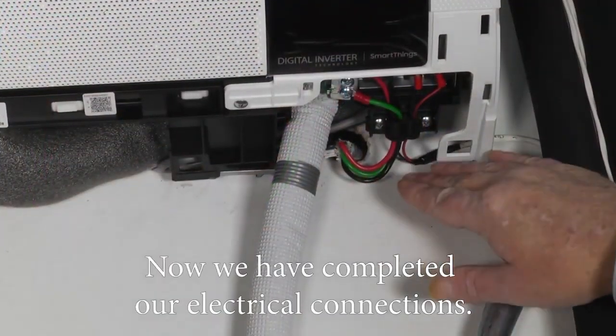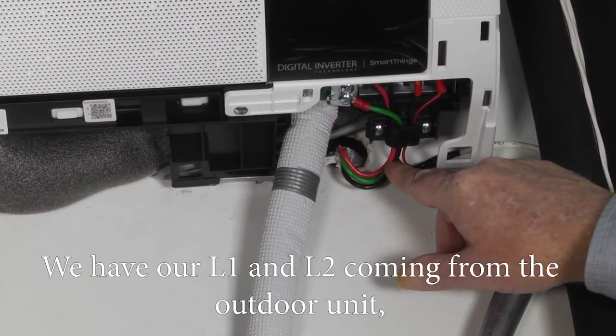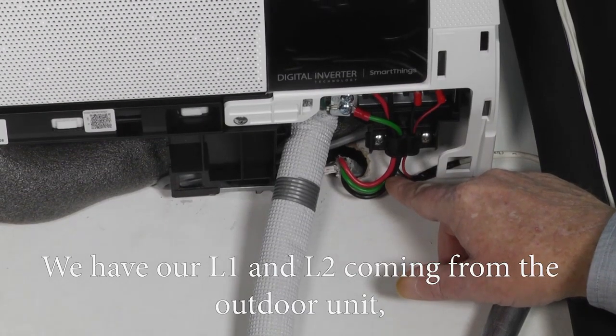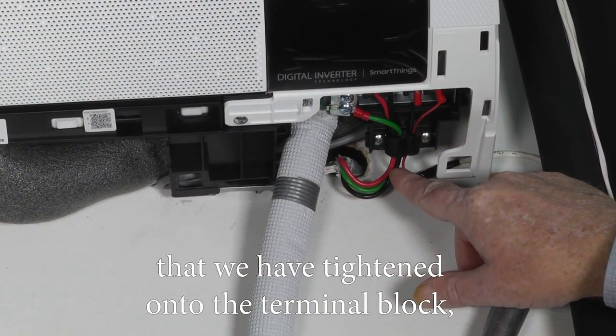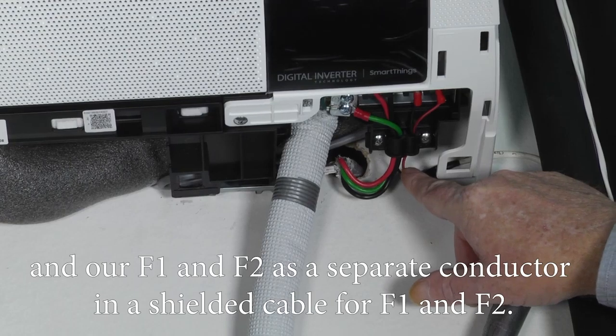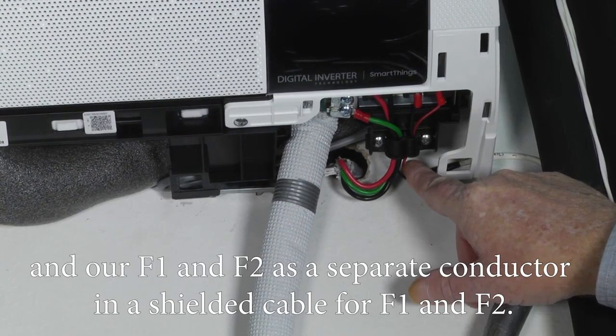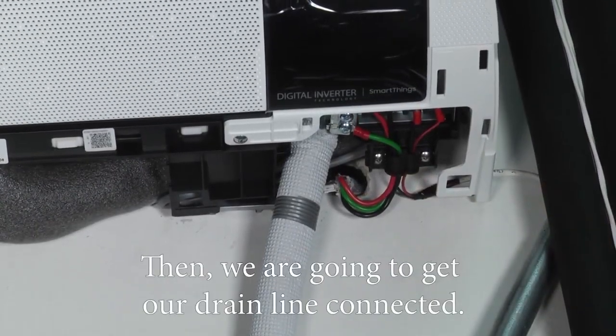Now we've completed our electrical connections. We have our L1, L2 coming from the outdoor unit that we have tightened onto the terminal block, and our F1, F2 as a separate conductor and a shielded cable for F1, F2. And then we're going to try to get our drain line connected.